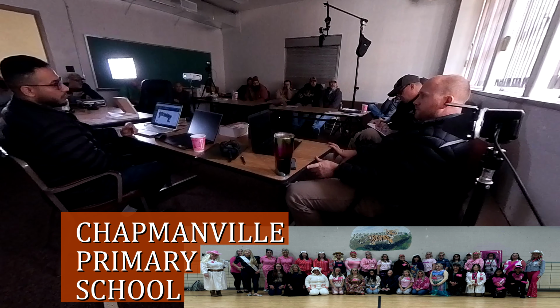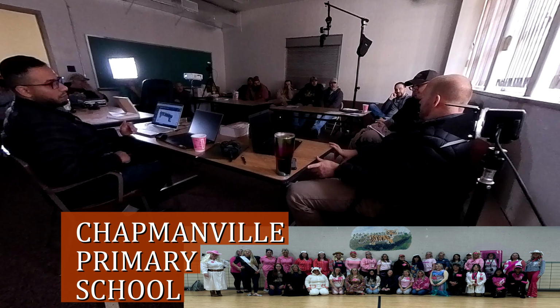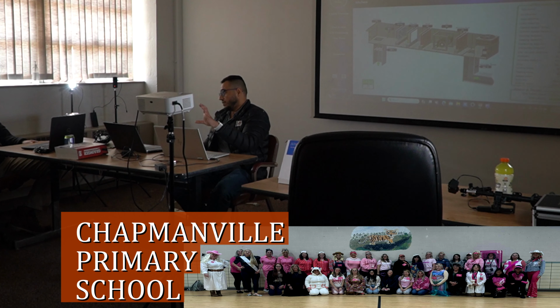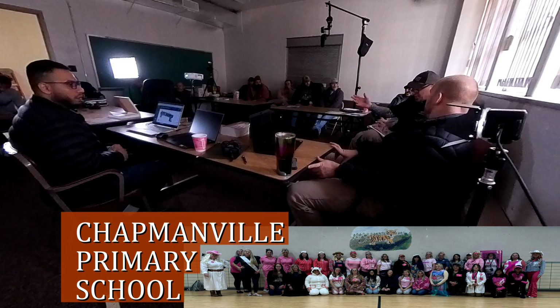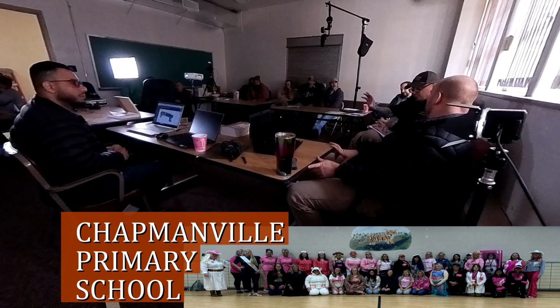I think Chapmanville Regional shows. You can look at your minimum position that's being set. It's being set for 10%. You can go up to 15, like 1.5. Say somebody's messed with it, we should know what it should be, you know what I mean? Those information of the minimum value, after the balancer created his final report, you need a copy of that information. If somebody deleted the value of the minimum position and you don't know what it is at this point in time, you probably need that reference. And we can put those also inside the VAS, so you never lose it, okay?